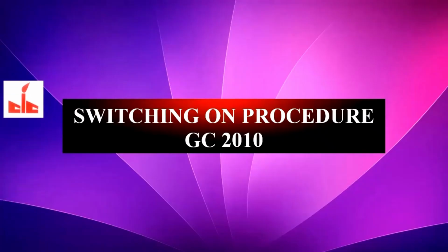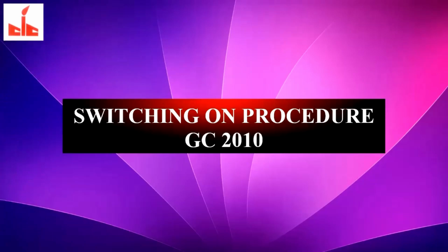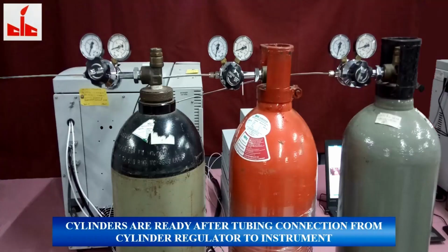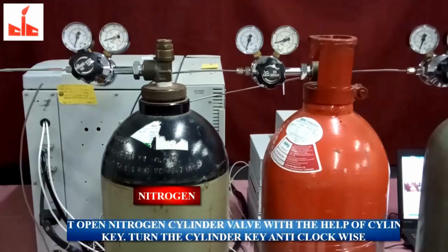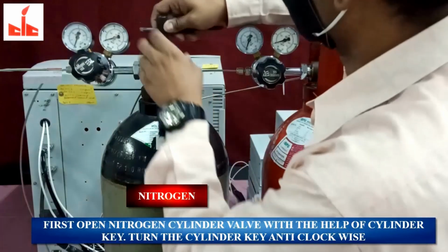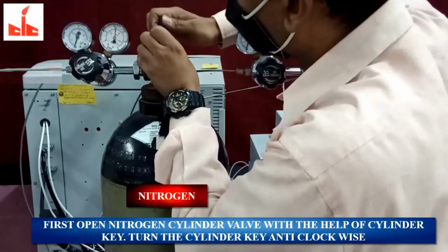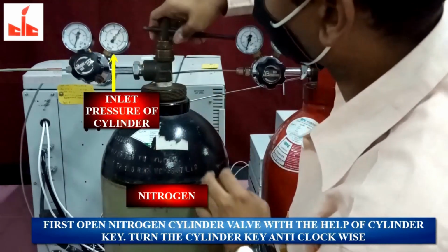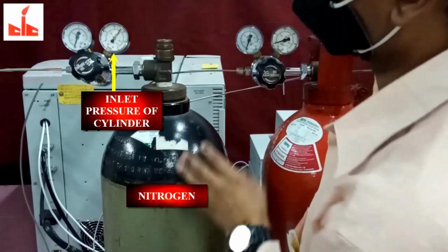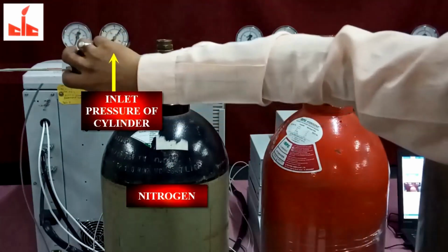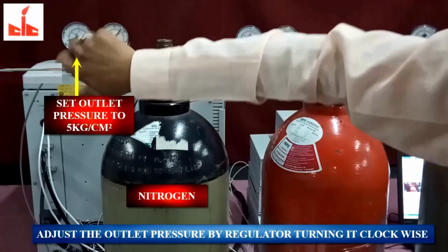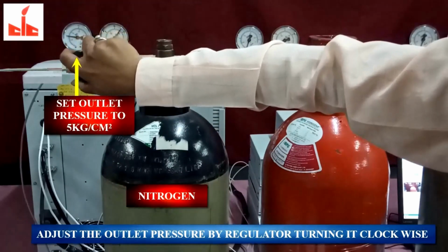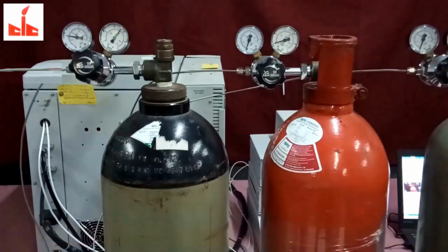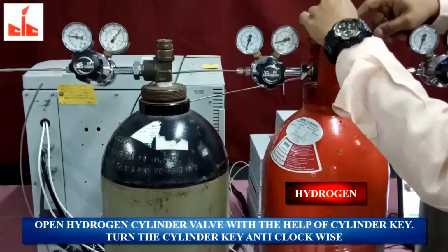Switching on procedure of GC 2010. Cylinders are ready, after tubing connection, from cylinder regulator, to instrument. First open nitrogen cylinder valve, with the help of cylinder key. Turn the cylinder key anti-clockwise to open it. Right side pressure gauge shows the inlet pressure of cylinder. Adjust the outlet pressure by regulator, turning it clockwise and set it to 5 kg per centimeter square.